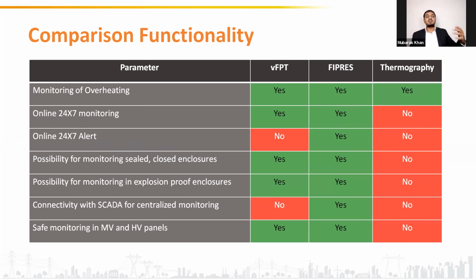Do these technologies monitor overheating? VFPT, yes, it monitors. FIPRES, yes, it monitors overheating. Thermography also monitors overheating. Even if you touch with your finger, you'll be able to detect overheating, right? You will get a shock, that is secondary, but definitely you'll know it is hot. Now, apart from jokes, online 24/7 monitoring: with VFPT, yes. With FIPRES, yes. With thermography, no, we are not getting any online monitoring. It is only periodic.